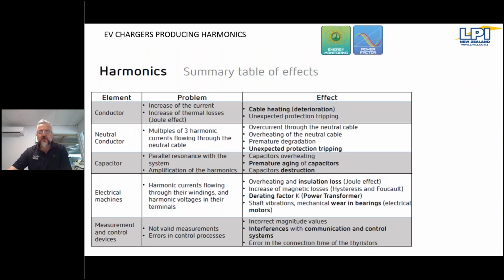For those of you that are not familiar with harmonics, I'll just quickly go over it. Especially for facility managers, it's quite important to realize that harmonics can cause some quite serious problems. If you're introducing, let's say, 2 or 3 big DC chargers at your facility, there is a possibility that you would introduce harmonics, and harmonics in the system can produce cable overheating, and they can also become a potential fire hazard. So it is important that you know exactly which way you're heading and what will be the final result of your installation. We can assist, and we did assist a number of different companies by assessing the situation and seeing what the capability of the system is, and if they're introducing EV chargers, what the options are to successfully introduce the number of required chargers.